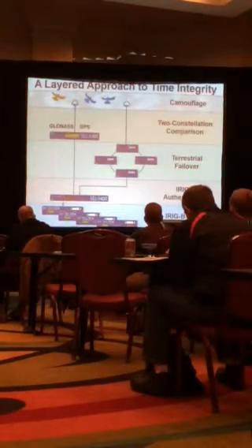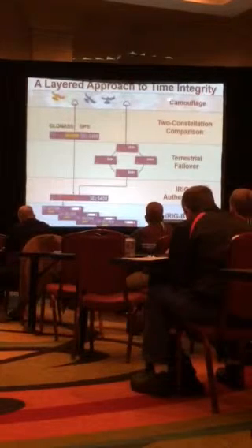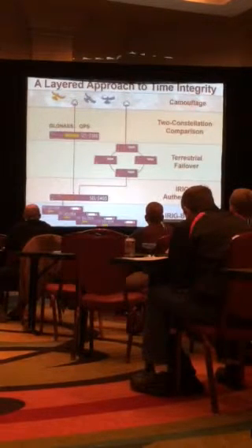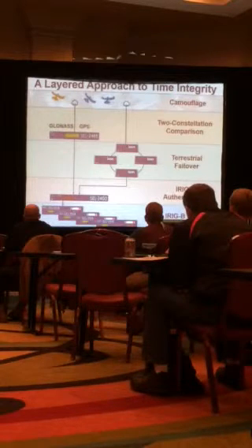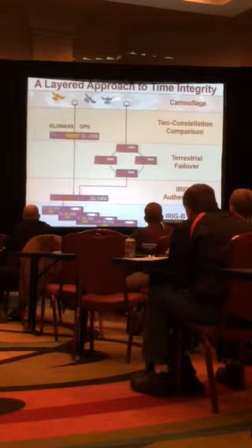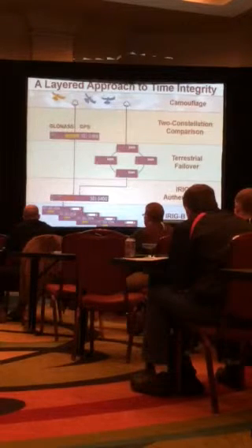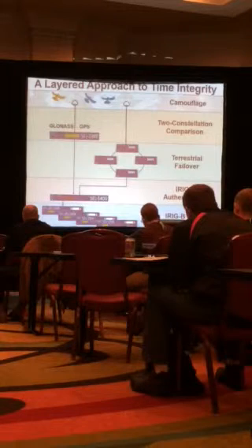So here's another way for time integrity. One thing to do is, I think it's a pretty good idea not to stick the antenna in plain sight. So you put it up high enough where maybe nobody can notice it. And that's a first defense. If you've got two antennas, you put them in different corners so it's a little harder for a bad guy to jam them both. And by the way, I'm not being alarmist about this. I'm being practical about it.